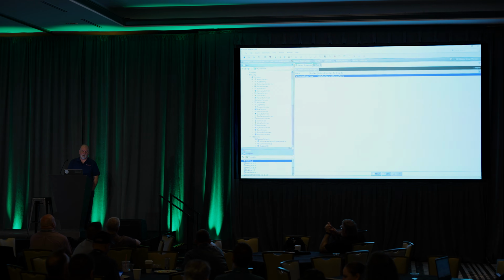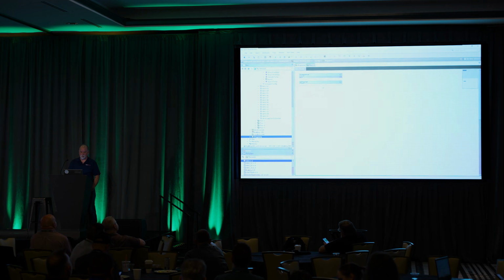Now, one thing that a lot of people mention is there's effort involved, right? I have to go put those tags on all these things, okay? So from an efficiency standpoint, if I was really trying to do that, I would probably use a program object, for example. I have a program object that would let me go look under the LON network for history config components here, and I could look for ones with a specific parent name or something, and then I could tell it to add a tag, and this would use B format.